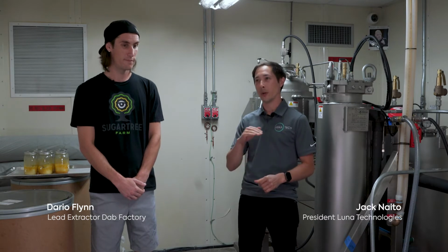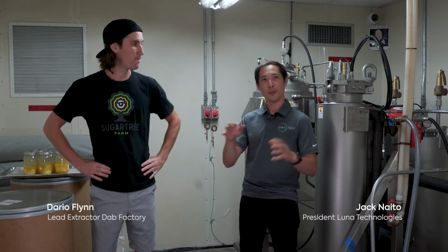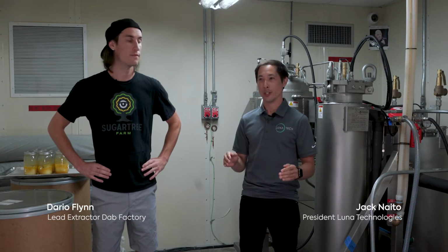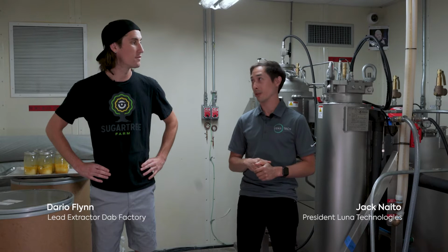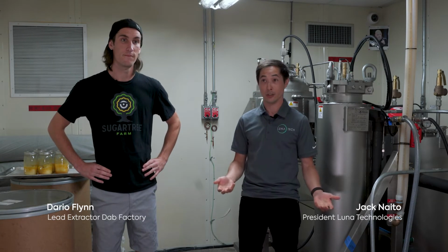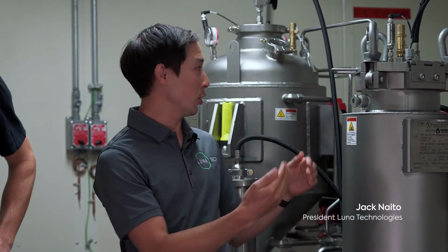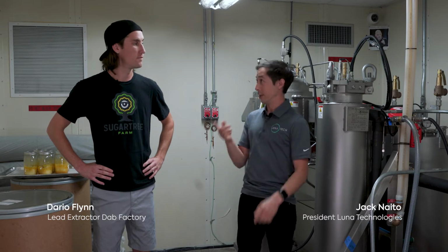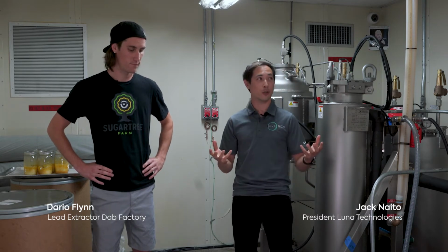The C1D1 rating is the highest rating of explosion limits, which means a lot of engineering goes into every single piece of electrical equipment you see in this room, making sure there are no ignition sources. C1D1 means we assume at all times there's an explosive level of vapor in this space. That's not the case right now since we shut off and isolated the equipment to film, but the normal assumption is there's always an explosive level of vapor. So we control that by ventilating, and by making sure all the electrical can't create a spark no matter what happens.